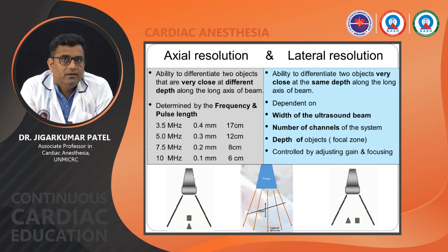And the third factor is the depth of the object. At the focal zone, there is a maximum concentration of the ultrasound beam, so you will get the best resolution at the focal zone. You can adjust this lateral resolution by controlling gain and focusing.